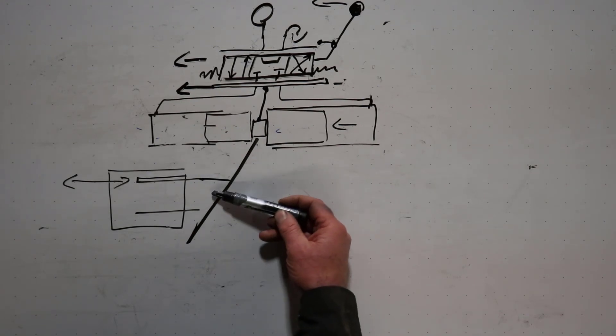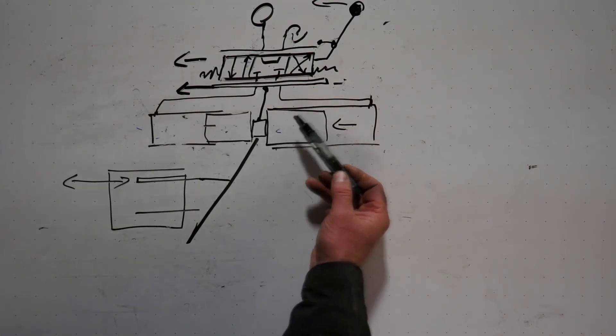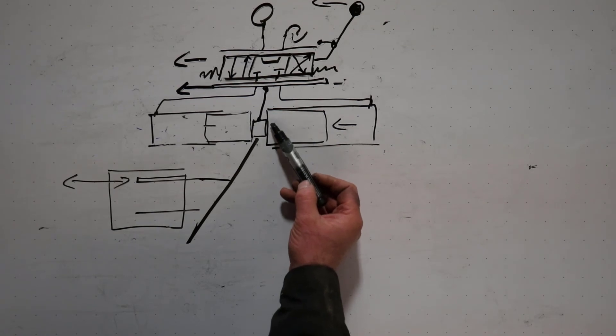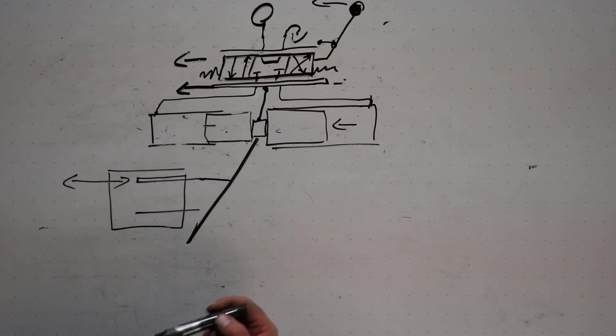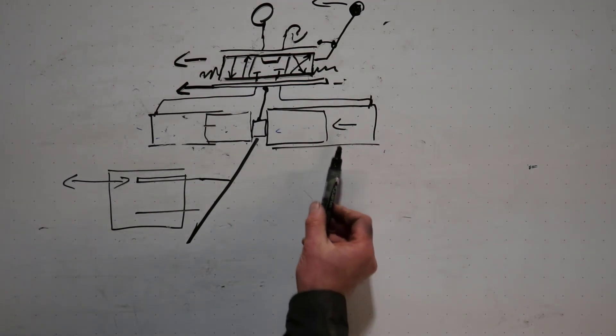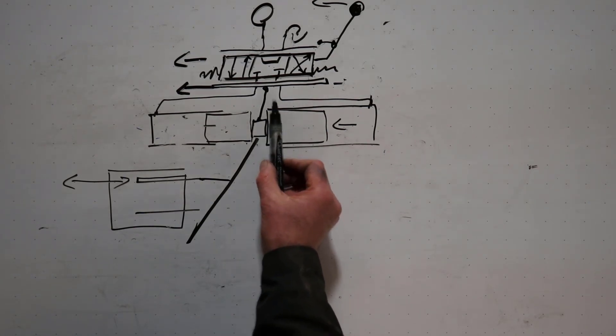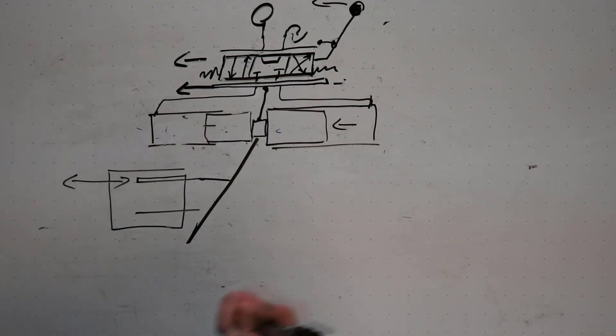So there's my hydraulic pump, the swash plate, the cylinder, the servo cylinder hooked to it. And we're using this little valve control of the cylinder. And this here is a feedback linkage. So it has a feedback to it. So I ask the pump to move a little bit. Once the pump physically moves that little bit, it shuts off, gives us our feedback. So the operator doesn't have to constantly adjust speed. He can push it halfway and we'll get half flow. Pulls it back a quarter, we get a quarter flow. There's no worrying about trying to find the happy spot.